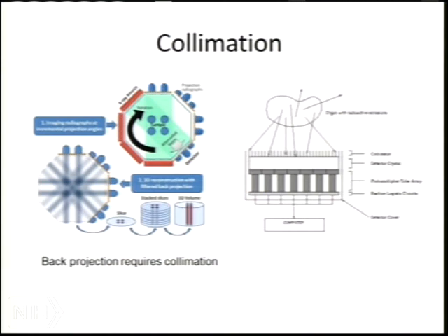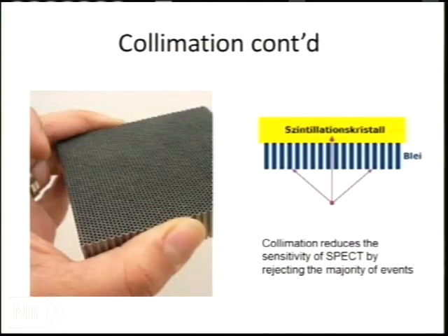So you run it through this collimator, and then there are the crystals that detect the activity, and then you can form an image off that. So this is what a collimator looks like. It's actually often made out of tungsten, and they're deep holes, and you can see that a gamma ray has to go down one of those tunnels to get to the detector. If it doesn't go through there, if it's at an angle, it'll be blocked.